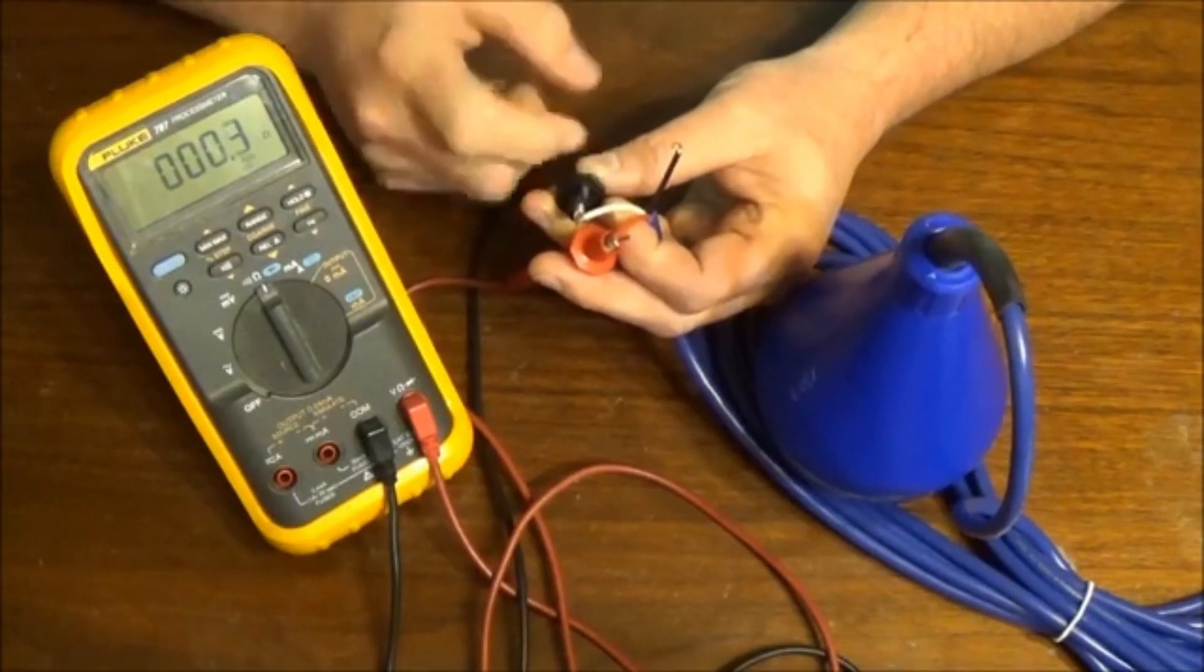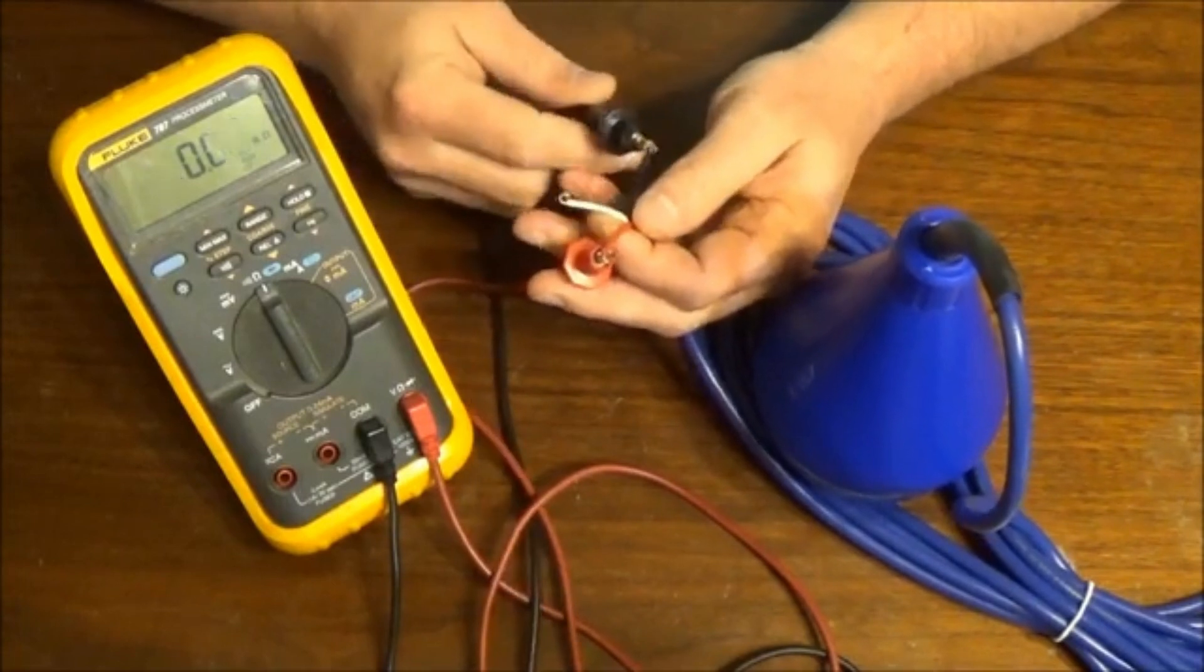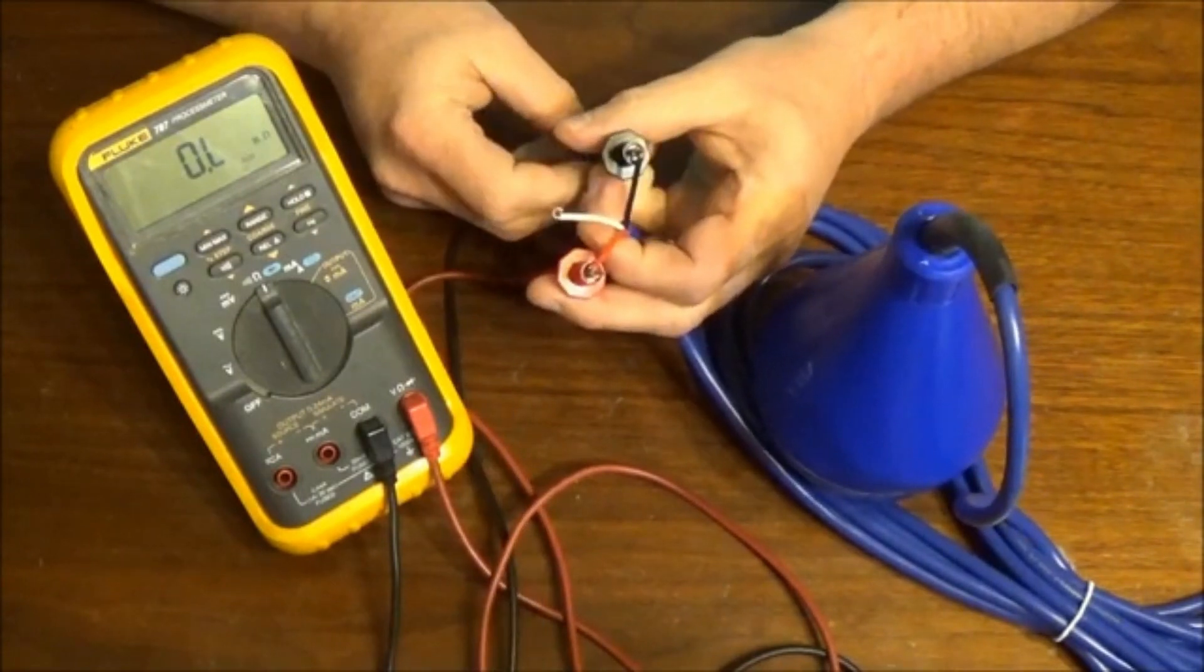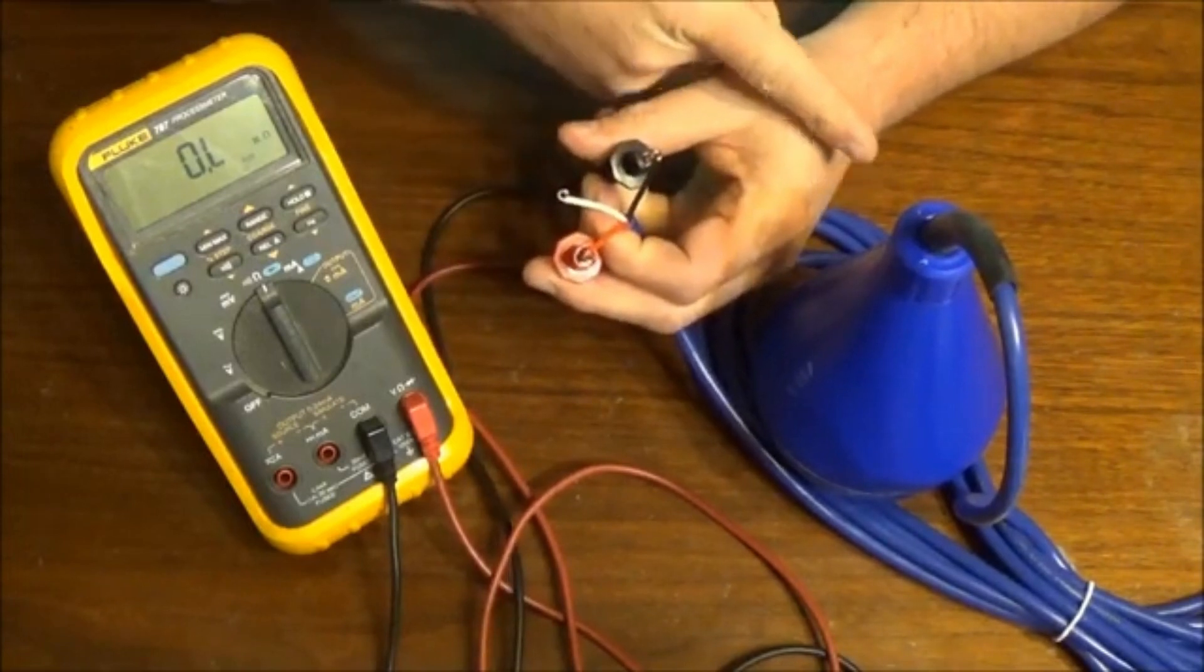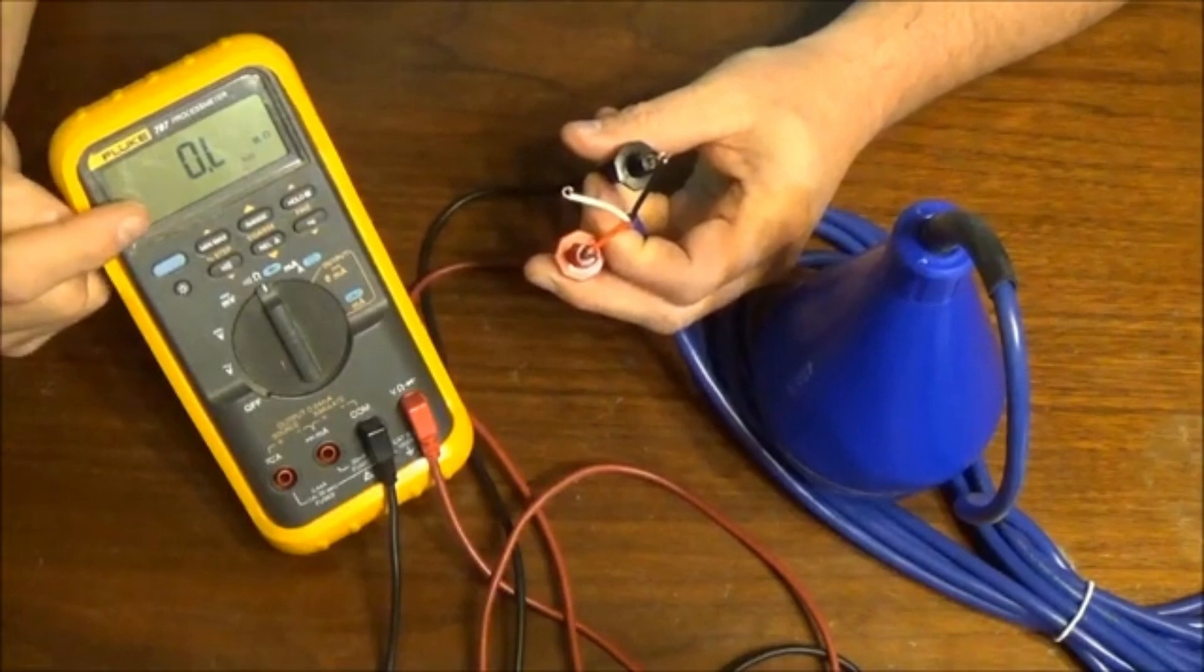Now, if we leave our lead on the red conductor, move to the black, we should see just the opposite. The float is in the upright position. The meter is reading an open condition.